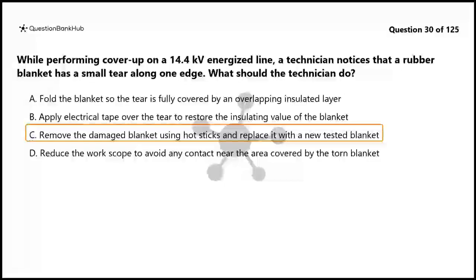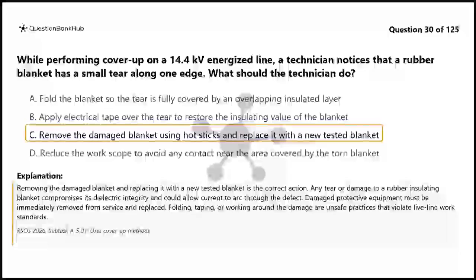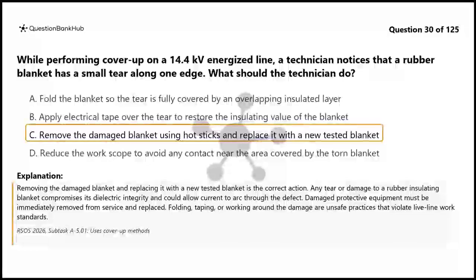The correct answer is C. Removing the damaged blanket and replacing it with a new tested blanket is the correct action. Any tear or damage to a rubber insulating blanket compromises its dielectric integrity and could allow current to arc through the defect. Damaged protective equipment must be immediately removed from service and replaced. Folding, taping, or working around the damage are unsafe practices that violate live-line work standards.